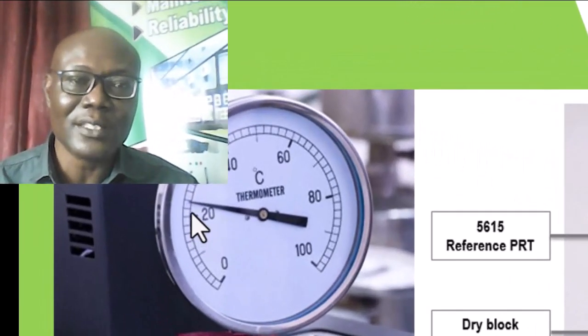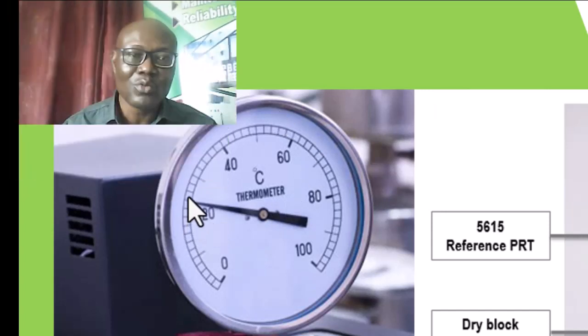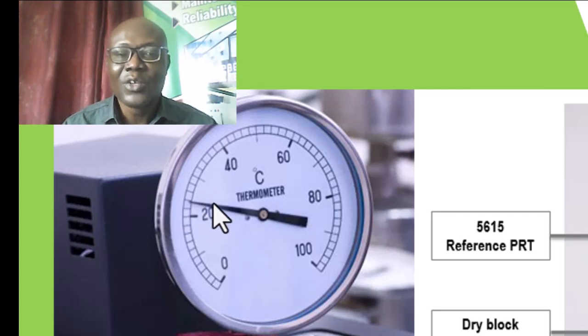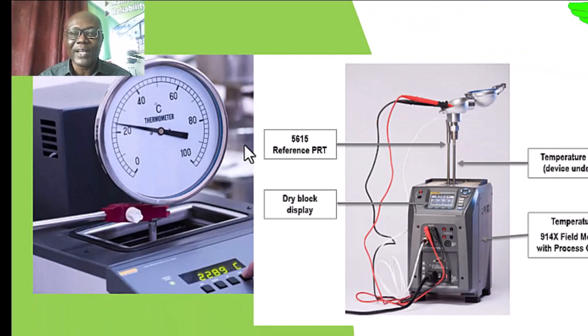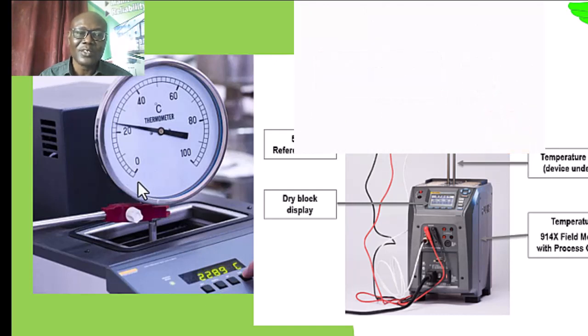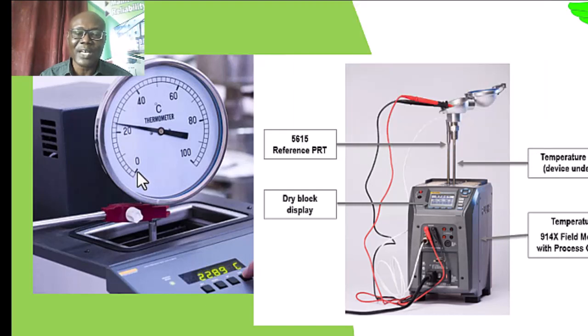And then when we look at the reading here, we see it's about 24, 20, 22, 24, 26, 28, 30. So it's about 24 degrees Celsius. So if it is within limit, fine. If not, we make correction or adjustment. We'll do zero and span adjustment. That is, when the temperature of the bath is 0, we'll look at the temperature on the gauge. If it is 0, fine. If it is not, we'll make adjustment.